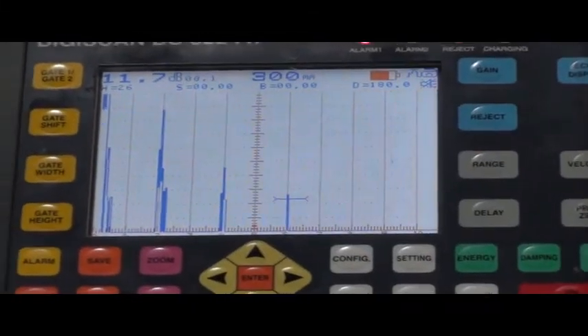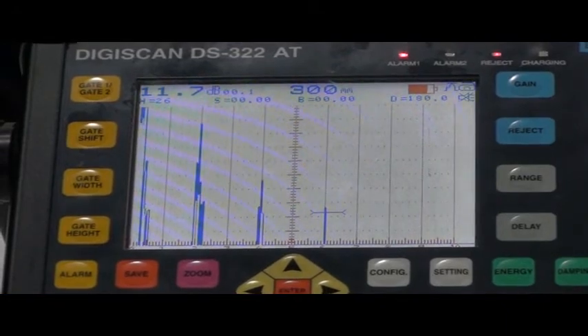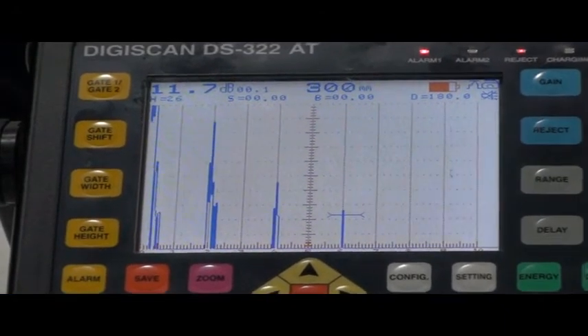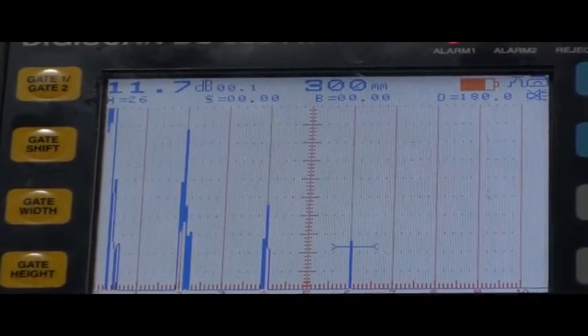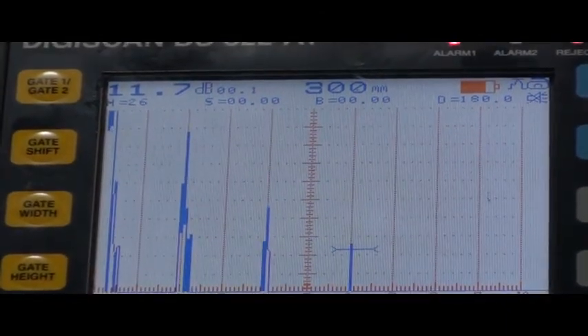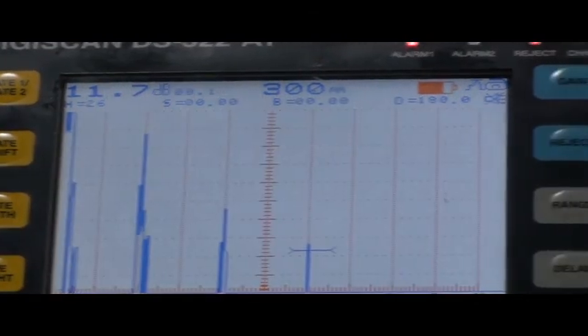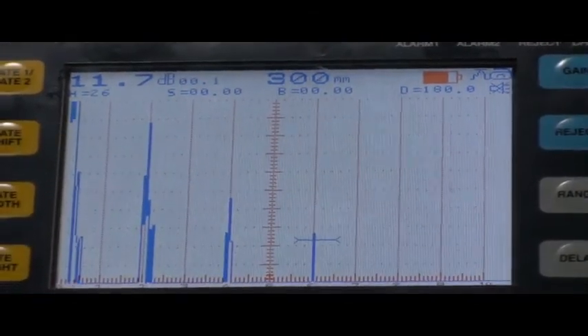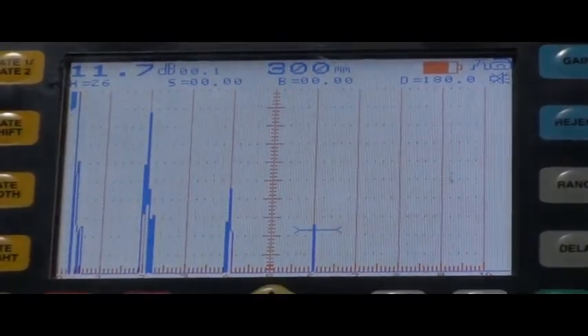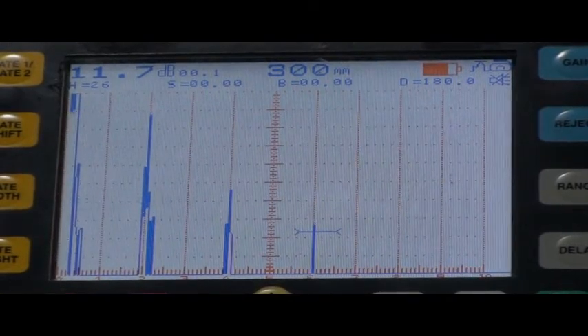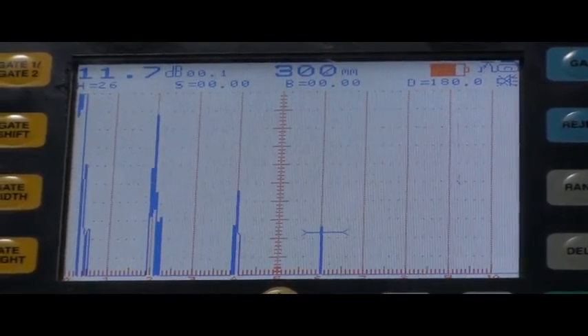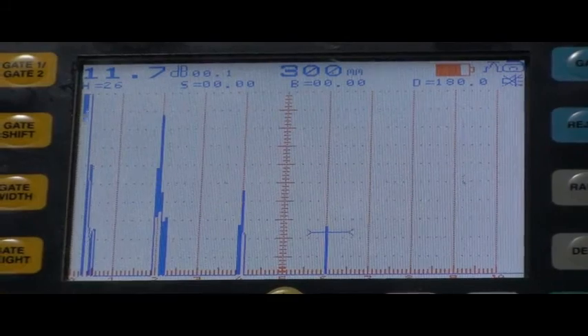Like that, we have to take 3 readings and calculate the average. It should be within the limit. If it is beyond the limit, we cannot rectify it — it should be sent to the original equipment manufacturer. This is the complete process for checking the linearity of amplification.